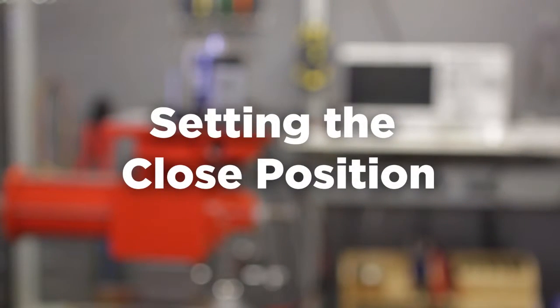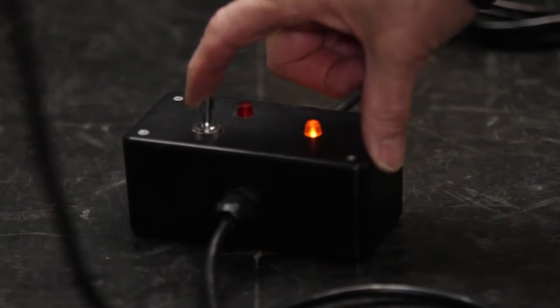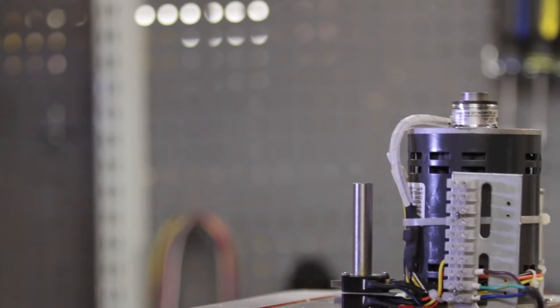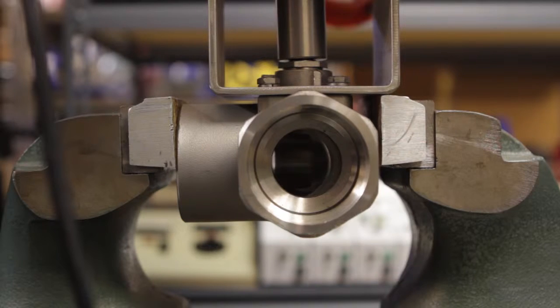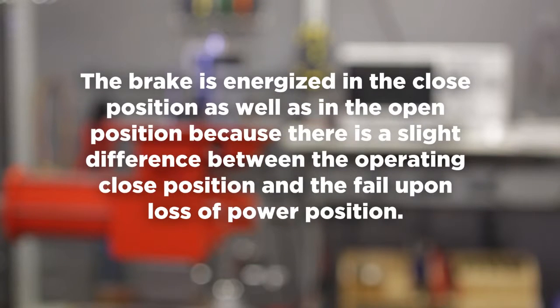To set the closed position, apply power to terminals one and three, and the actuator will begin to run in the clockwise direction. When the actuator reaches the closed position, the limit switch changes state and de-energizes the motor while energizing the brake. The brake is energized in the closed position as well as in the open position because there is a slight difference between the operating closed position and the fail upon loss of power position.